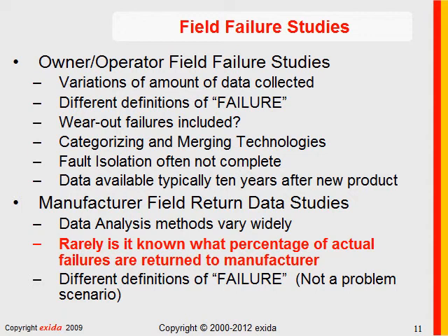For owner-operator field failure study, there could be variations in the amount of data collected. I have found different definitions of what is a failure. Are wear-out failures included or not? I've seen many of these studies where they categorize broadly and merge different technologies, giving you results that aren't appropriate for any of the technologies. I've seen fault isolation often not complete, in other words, very poor root cause analysis.